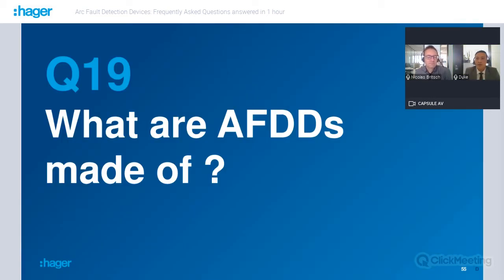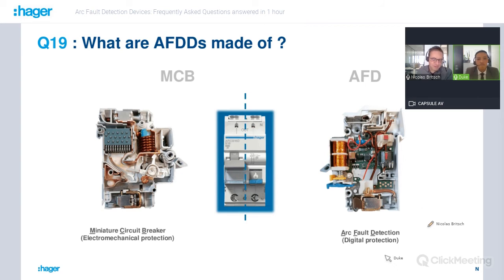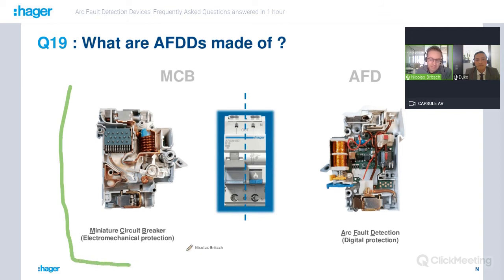So we have already seen different aspects of the product from outside. Now, what are AFDDs made of from inside, please, Nicolas? So you want to have a look inside the product, of course. An AFDD is not just an arc fault detector. It also has conventional overload and short circuit protection on the MCB part here on the left, and sometimes also residual current protection. So you will see it in the next product. This first kind of product is an MCB plus AFD product.